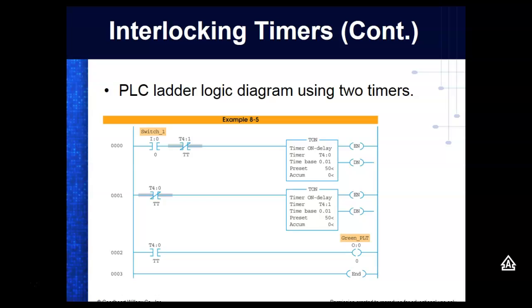So what's the three types of timers we have? Two categories. We have two categories. What's the two categories? Somebody said off delay and on delay. But we have three timer instructions. We have a non-retentive on delay. We have a non-retentive off delay. And then we have a retentive on delay. So your non-retentives, those guys are going to reset instantly, right? Okay. Your retentive, you're going to have to reset it.